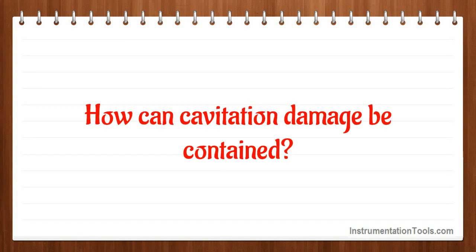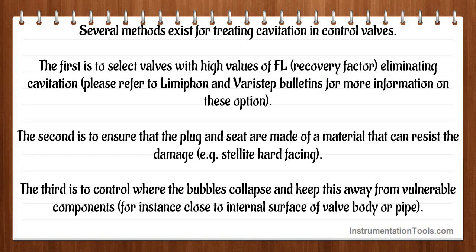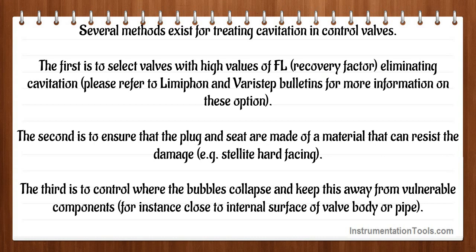How can cavitation damage be contained? Several methods exist for treating cavitation in control valves. The first is to select valves with high values of the pressure recovery factor, eliminating cavitation. The second is to ensure that the plug and seat are made of a material that can resist the damage, e.g., stellite hard facing. The third is to control where the bubbles collapse and keep this away from vulnerable components, for instance close to internal surfaces of the valve body or pipe.